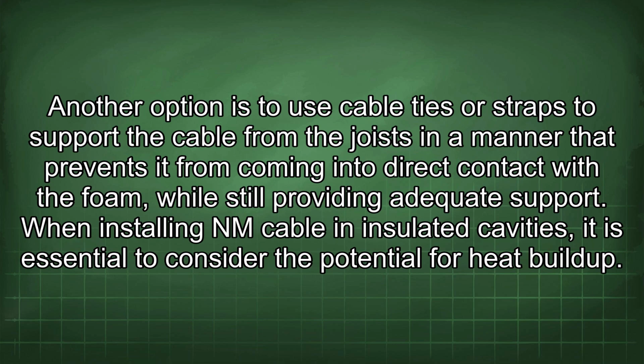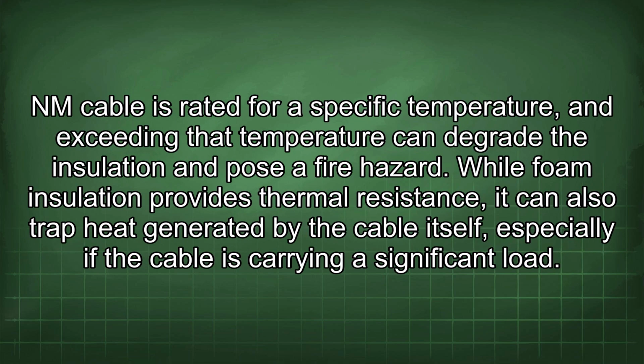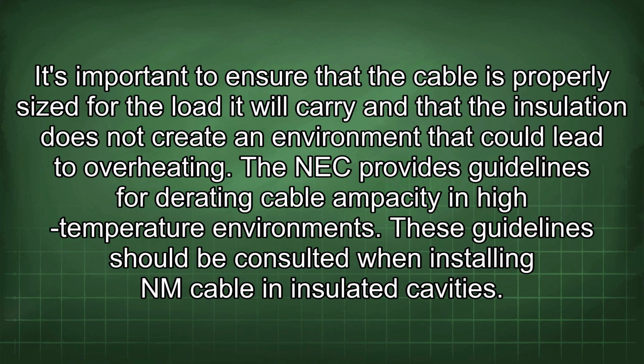When installing NM cable in insulated cavities, it is essential to consider the potential for heat buildup. NM cable is rated for a specific temperature, and exceeding that temperature can degrade the insulation and pose a fire hazard. While foam insulation provides thermal resistance, it can also trap heat generated by the cable itself, especially if the cable is carrying a significant load. It's important to ensure that the cable is properly sized for the load it will carry and that the insulation does not create an environment that could lead to overheating. The NEC provides guidelines for derating cable ampacity in high-temperature environments. These guidelines should be consulted when installing NM cable in insulated cavities.